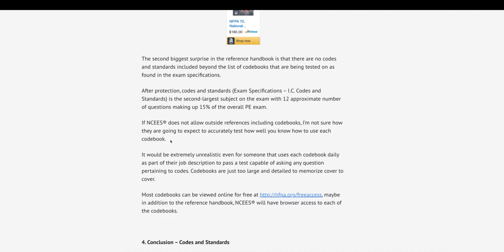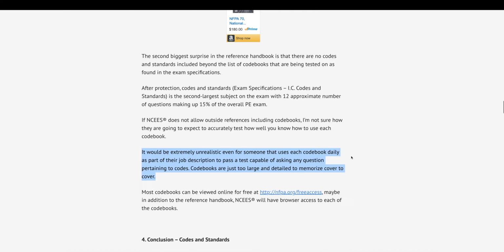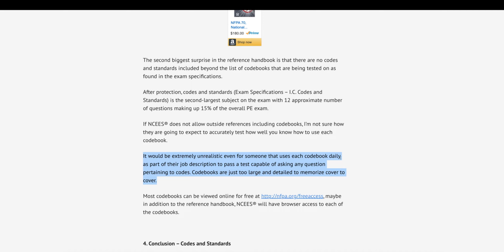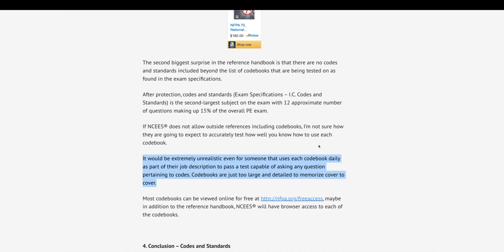So this is really interesting. Codes and standards is the second largest topic. It would be extremely unrealistic, even for someone that uses code books daily, to be expected to accurately answer code questions without having the code book next to them. Even just thinking of aspects of the code book, especially the NEC code book that engineers use most often, think of the transformer overcurrent protection table. I'm sure everyone listening to this has used that table, either on the job or studying for the PE exam, to maybe size a fuse or a breaker for a transformer, either upstream or downstream, primary or secondary overcurrent protection.